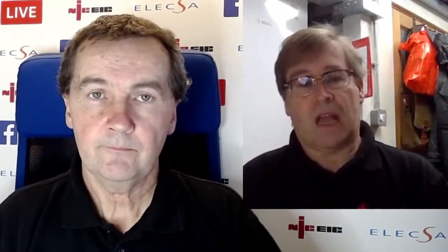So let's talk a little bit then about what the key differences are. What's the key characteristic that's different across the B, C, D range? Well, when we talk about Type B devices, Type C devices and Type D, we're talking about the instantaneous tripping current. So with a Type B device, that will trip anywhere between 3 and 5 times its rated current. So for a 6 amp device, it's going to be anywhere between 18 and 30 amps. Yep. So for a Type C device, it's between 5 and 10 times its rated current. So if you were talking about a 10 amp breaker on a Type C, that will trip anywhere between 50 amps and 100 amps. And so on. So with a Type D device, you'll trip anywhere between 10 and 20 times its rated current.